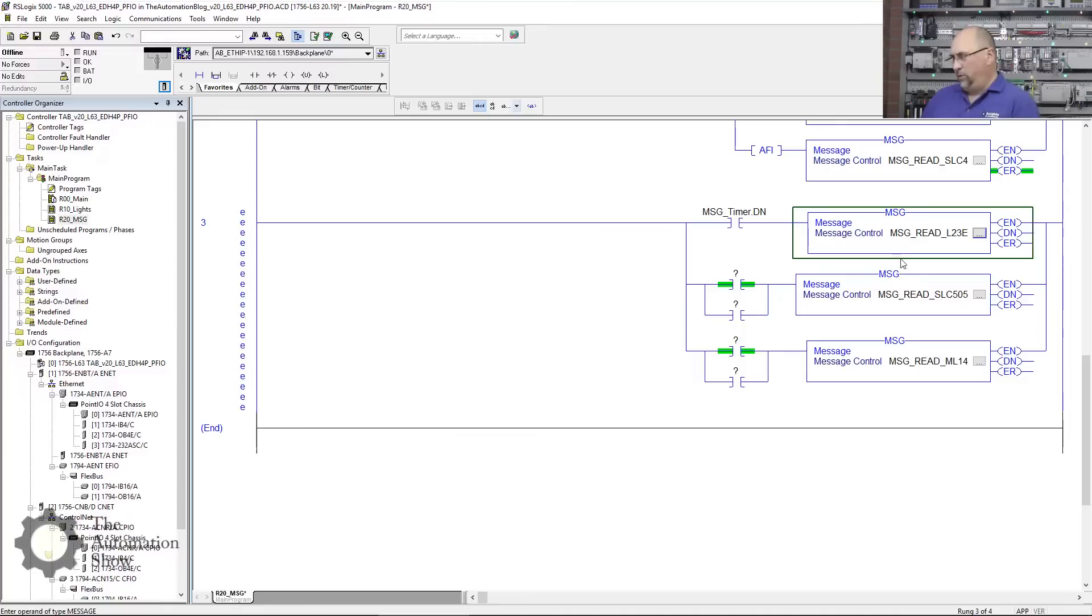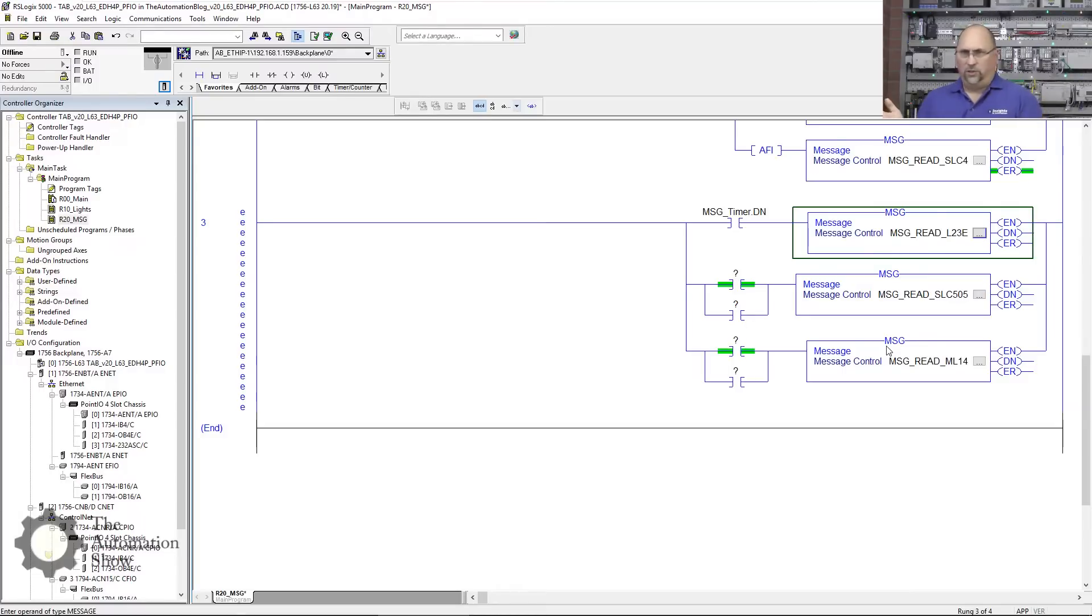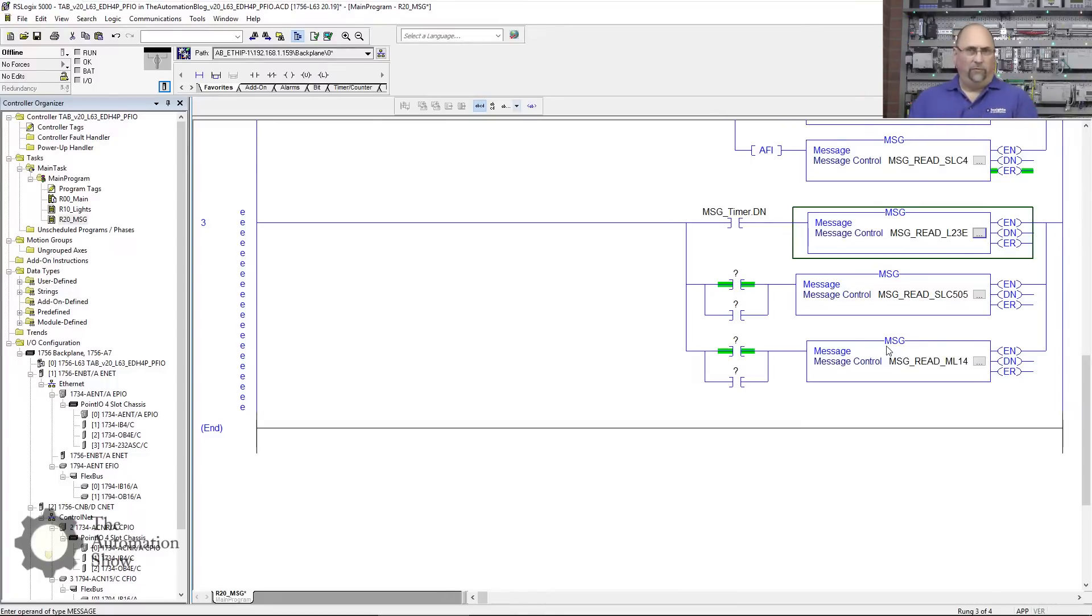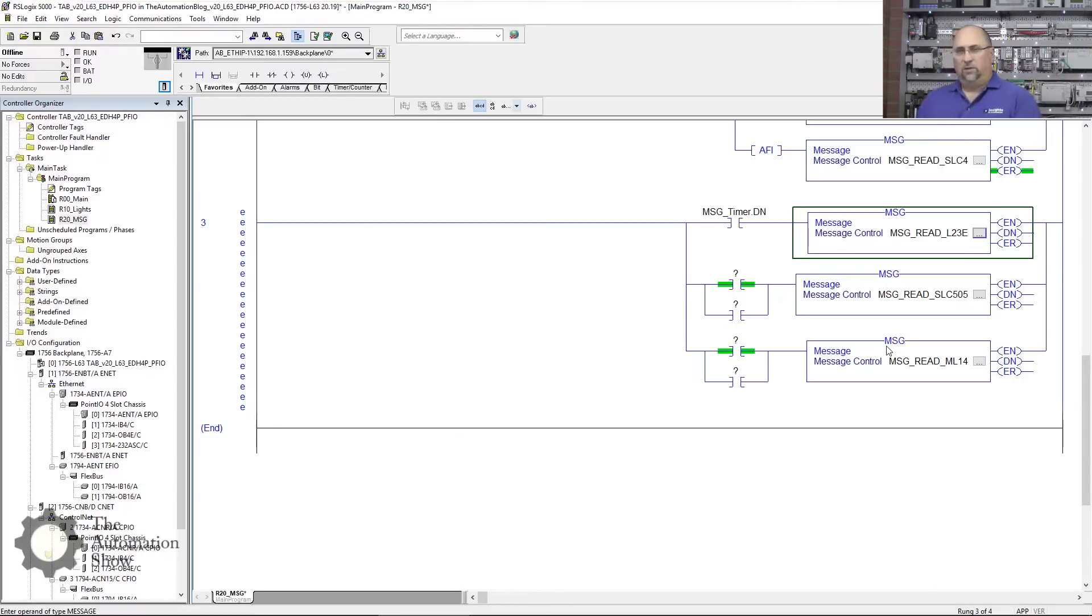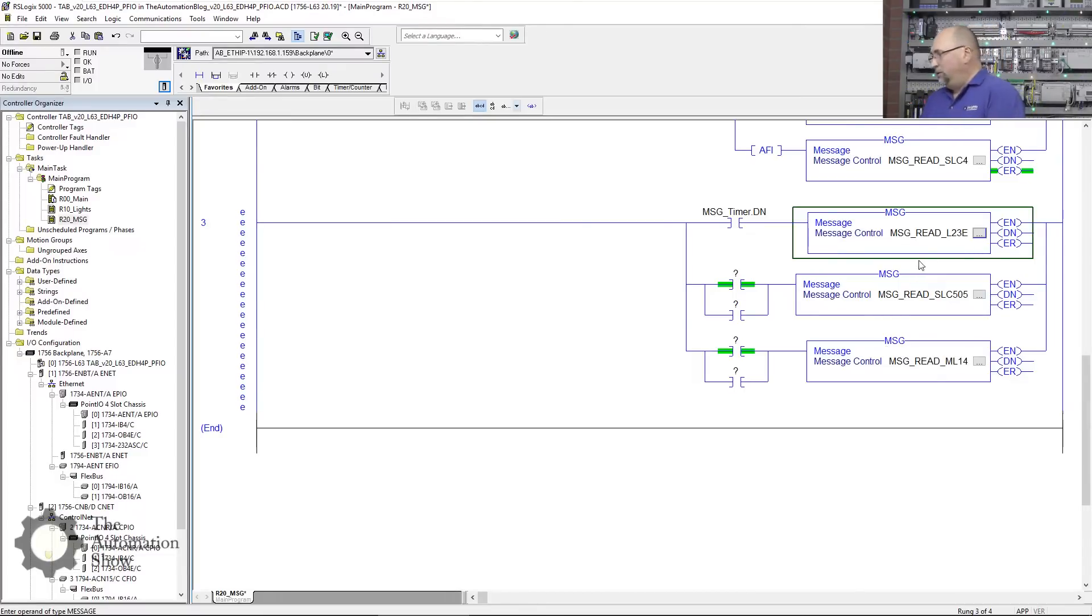That's the first one. Now what we want to do here is cascade these—we're going to interlock these so they don't all try to go at the same time. We know from our previous conversations that the Control Logix cannot send 100 messages at the same time; it can only do one at a time. We don't want to fill up the buffer and start losing messages, have messages thrown away. Kind of like when you fill up your keyboard buffer, anything you type gets lost. Same thing here—if you fill up the message buffer, everything gets lost.